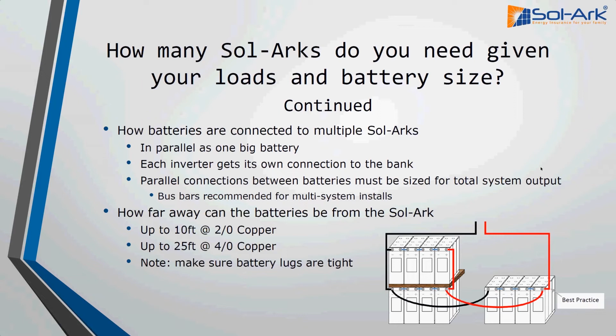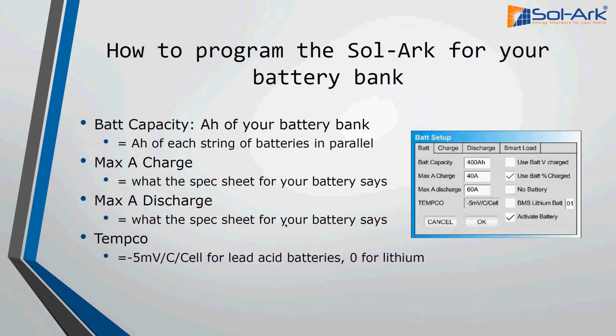Max amp charge and max amp discharge are exactly what they sound like: they limit how much power we pull out of or put into your battery bank, which is important for its longevity. Then there's the temperature coefficient, which we use mostly for AGM lead-acid batteries. Negative 5 is the default value, and that's fine for a lead-acid battery. But if you're using lithium, make sure you change that to 0, because we don't need to adjust for temperature with a lithium battery.